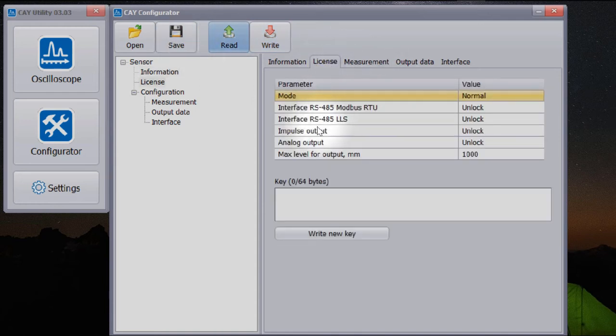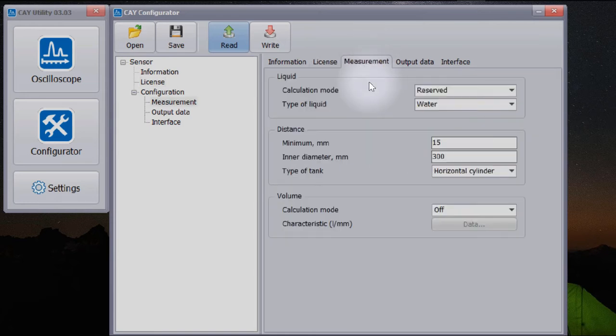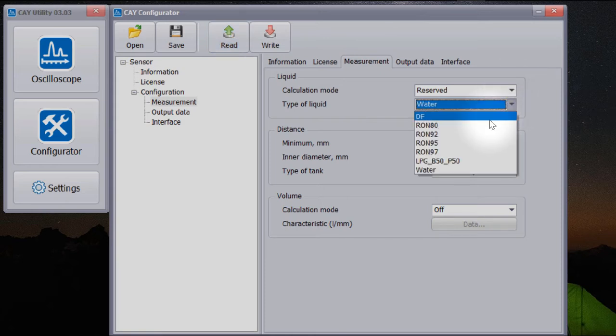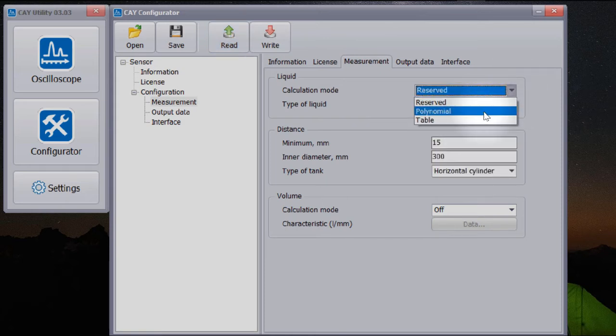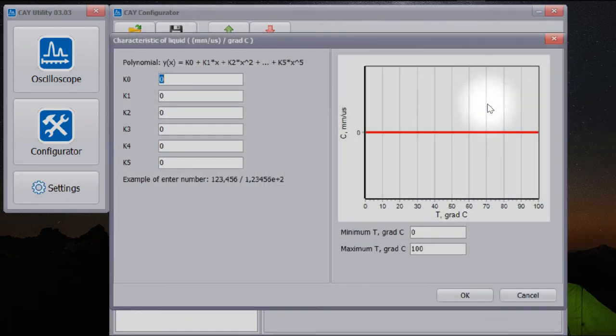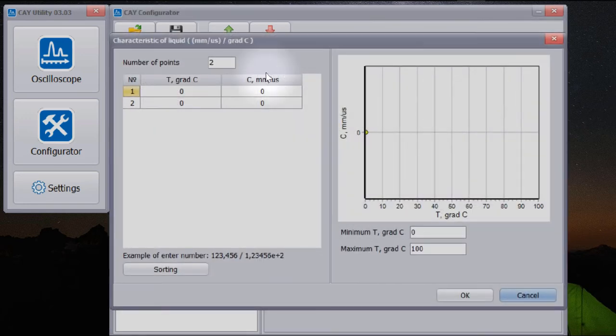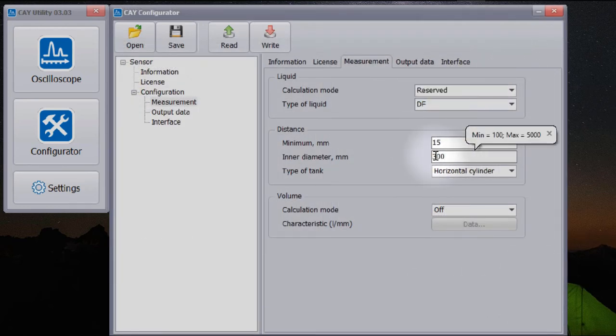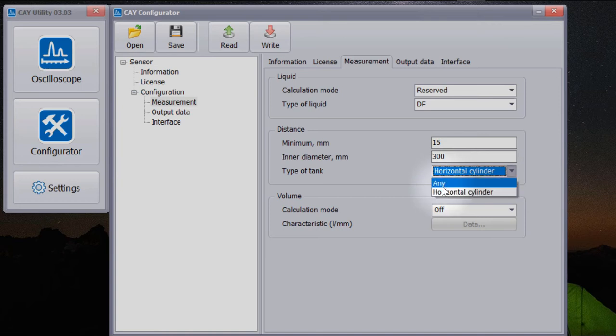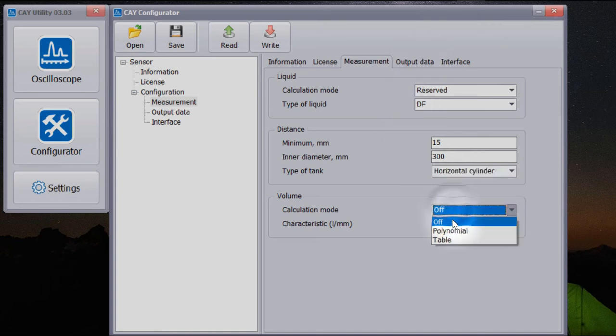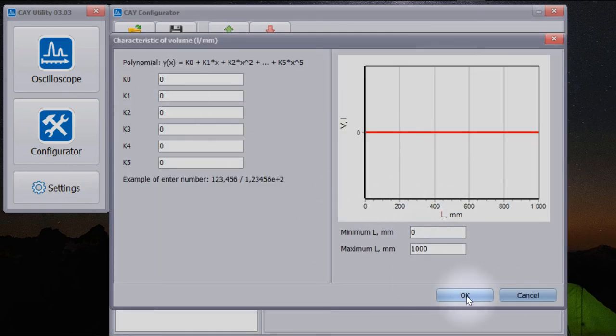On the License tab, we can see that this sensor can be used to measure level up to 1000 millimeters. We can choose the type of liquid. If you can't find your liquid there, we can set it up by polynomial or table information about acoustic speed as a function of temperature. Set the maximum level. Also, the type of tank. The tank calibration table can be stored in the sensor, so the sensor output will be proportional to the liquid volume. We can use either polynomial or table calibration data.